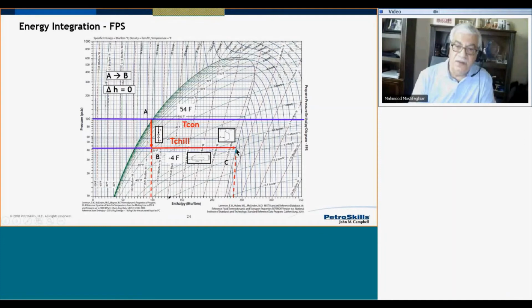Then I go to the compressor, compress the gas. I follow an isentropic path. This dashed red line, almost red or brownish color, is my constant entropy line. I don't care what the number is. I just follow one of them. So I start from here and follow one of them. If I don't have a line at the desired point, I keep an appropriate distance between the two constant entropy lines. Here's one of them, and I follow the path, maintaining the course till I hit the discharge pressure of the condenser.